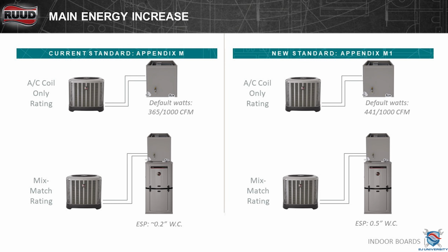Very seldom. Once you've added a filter in there, put a coil on top of that unit, you're typically not seeing 0.2 static. So what they've done and changed to SEER 2 is now they're rating it at 441 watts at 1000 CFM at a 0.5 static. So that's how we've gotten our SEER 2 rating, is they've changed the wattage and what the testing for the inches of water column across that external static is.